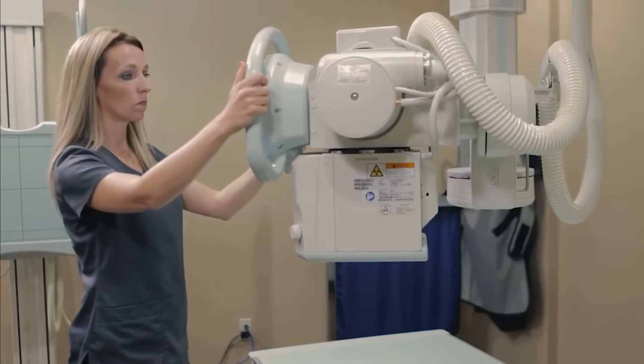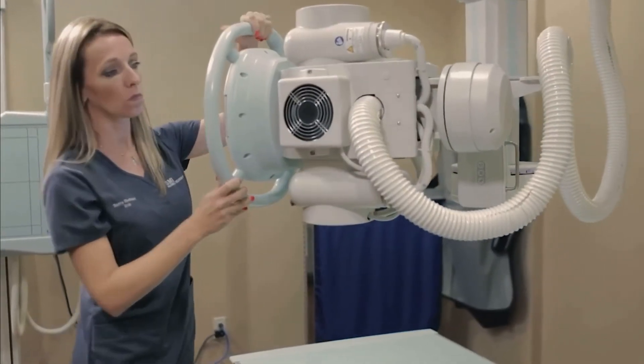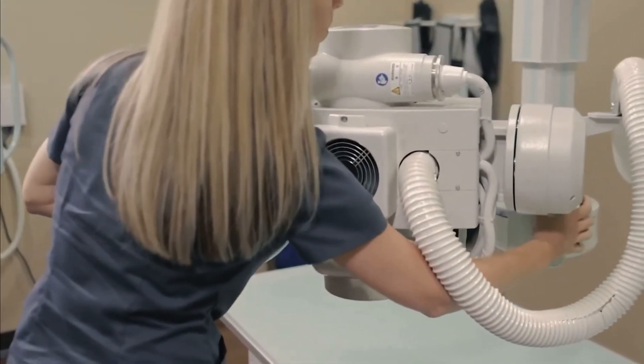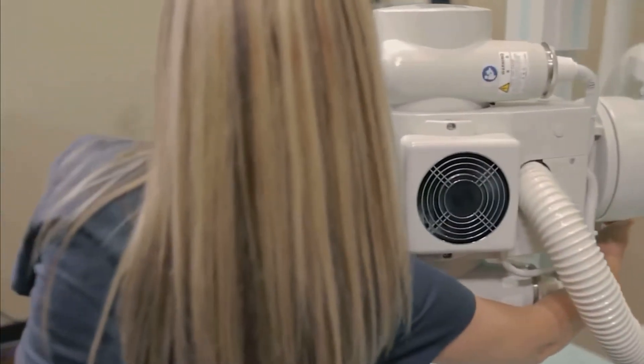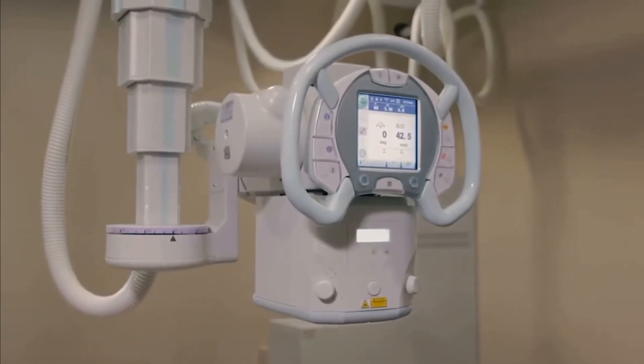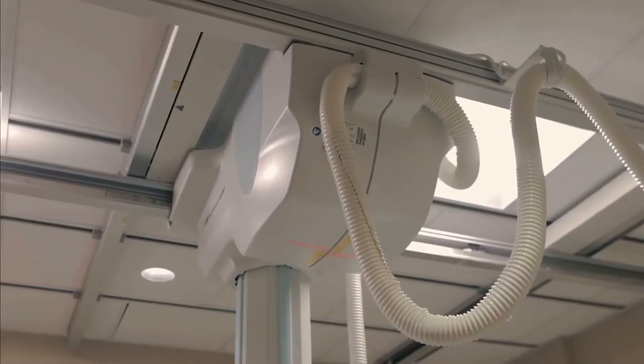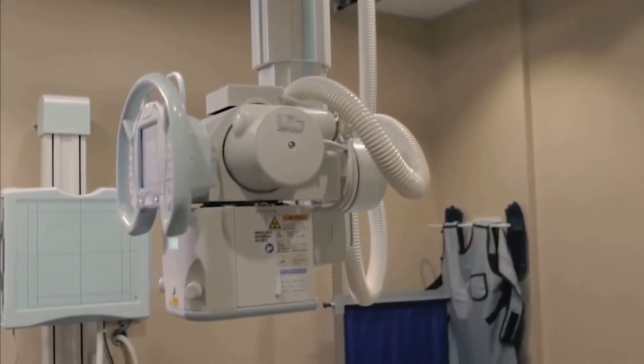The rear-mounted switches, located on the back of the overhead tube, allow for vertical access and rotation in any direction. With the addition of the collimator light switch, these extra buttons ensure the versatility needed to complete any emergency exam or cross-table work. The next-generation collimator reduces x-ray dose to patients by automatically switching to the optimal filter for each selected APR, minimizing unnecessary exposure while obtaining high-quality radiographic images.